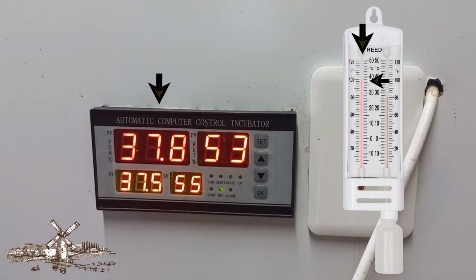Now, we've got to a point where our calibration is correct on temperature. We can see that the digital controller and our dry thermometer are the same. And we can now move on to the humidity calibration. For the humidity calibration, we are going to do exactly the same thing we did before on the temperature.